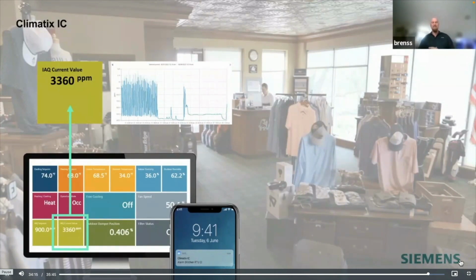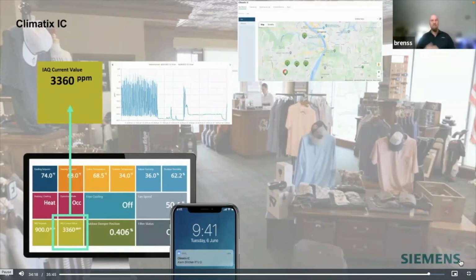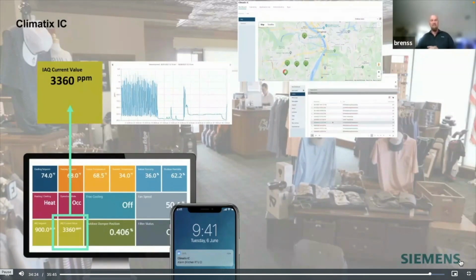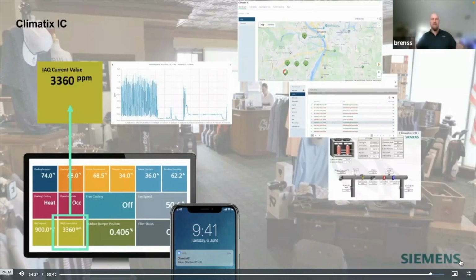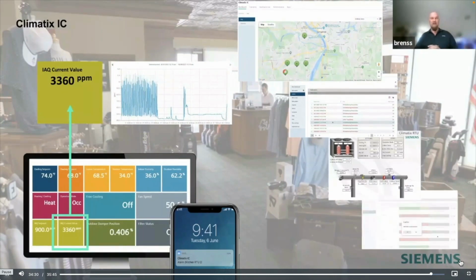So what was happening was, as we went a little bit further and started investigating, we looked on the map, we saw where this unit was, we went to the unit, and then we determined that below the sports shop at this country club, they were storing their golf carts, and on a giant heater in the ceiling, the flue actually rusted and broke off. And as it was running, it was just blowing the flue material up into this room, and that's what happened. We don't know how long this was going on, could have been for years, but in my personal opinion, we've kept people safe by putting in this system. And our system worked fantastic, and the country club owner was thrilled to hear about this.